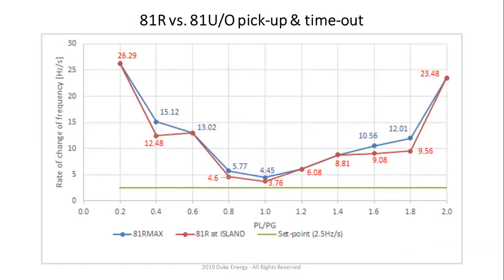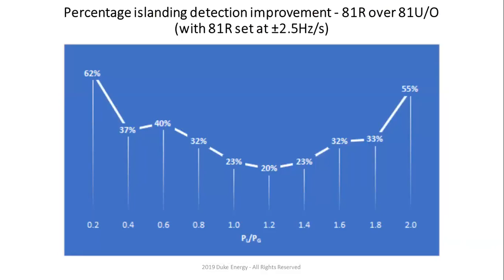So essentially, you can actually even torque control this setting if you want to, right? Interestingly enough, you can see over here that for 1.0 they're the smallest, the deviation from 2.5, which is what is expected, right? So in this case, you can clearly see that if you have 2.5 hertz per second, it works. Now, everything that you see over here is a function of a fault, but when you have 2.5 hertz, you've got to make sure that you don't trip for something that's temporary, right? So in this case, you can just see the percentage improvement if you use 81R at the 2.5 hertz setting.